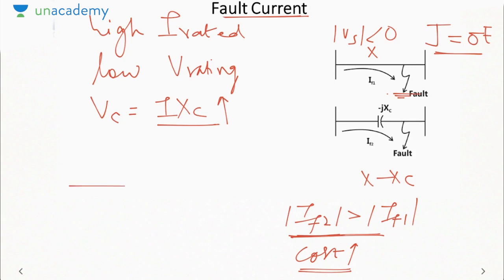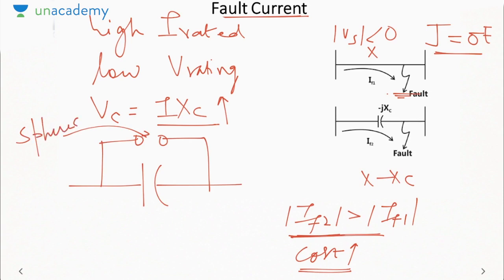So what we do is, with a series capacitor, we connect in parallel a sphere gap. This is called a sphere gap. Here two spheres are kept at some gap. So what will happen when the voltage across the capacitor is high? The electric field will also be high. Due to the high electric field, the air between this gap will ionize and current will start flowing through this path. So current will flow through this path instead of flowing through the capacitor. It finds an alternate route, and since it finds an alternate route, the capacitor is shorted and the capacitor voltage reduces. So that is how we protect the series capacitor against any damage in case of a fault.